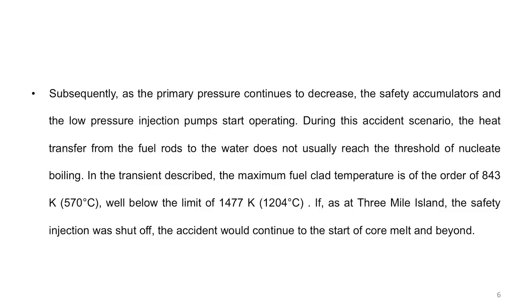We then bring in the safety accumulators and low-pressure injection pumps, which are designed for lower pressure. So there was a high-pressure injection phase, and now we go to low-pressure injection. Earlier, because flow was not sufficient, there was a bit of nucleate boiling in the core. But by the time low-pressure injection starts, it has come down. The maximum clad temperature is about 570°C, whereas the limit is about 1204°C.